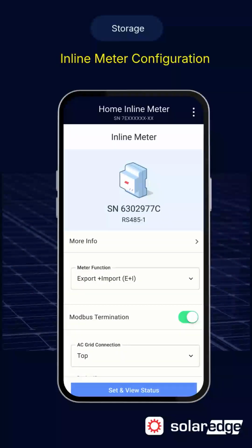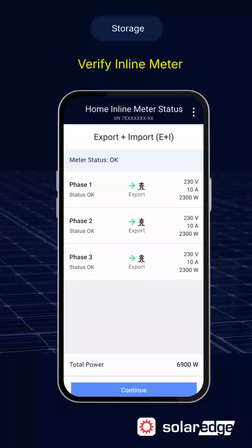Configure the inline meter according to the site requirements. Verify the meter function, then enable Modbus termination if this is the last device in the communication chain. When you're done, tap Set and View Status. Check that the meter status is OK and that all three phases are communicating correctly. Confirm that the voltage, current, and power readings match the expected installation values. When everything looks correct, tap Continue.